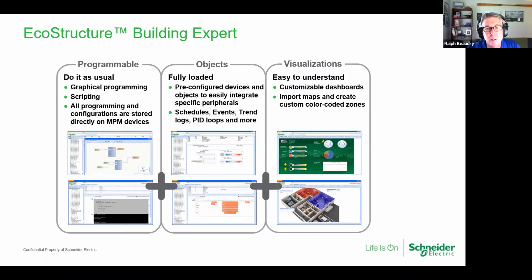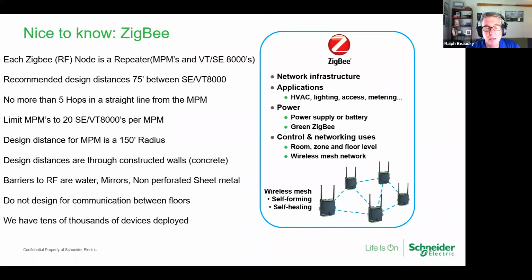When I go out to the room controller in the field, I'm going to put that PAN ID in for the gateway I want to communicate to. I'm going to put the same channel, and I'm going to give it a unique MAC address. So I'm recommending that when you design a job, you don't use more than 20 room controllers on a gateway. Is it possible to use more? It is. But what happens is you start degrading your signal strength, right? So not signal strength, but your transmission of data back and forth. And it really starts to bog it down. So I say design to 20, but if you have a job with 22 or 24, yes, we could do it off of one gateway. I wouldn't push it past 25 though. So, the hard stop should be 25, and then you've got to add a second gateway into your network, okay?